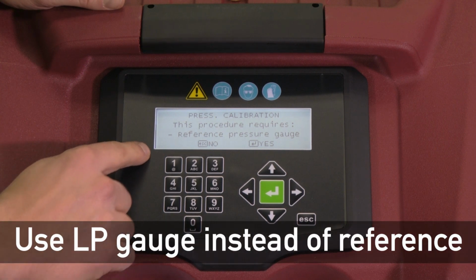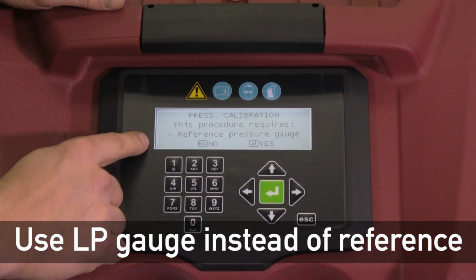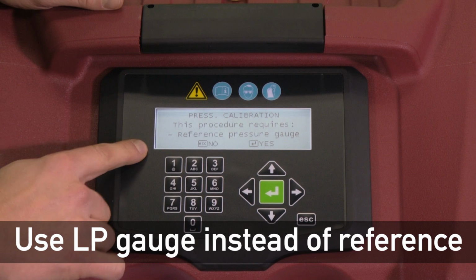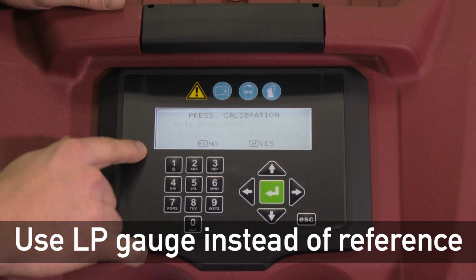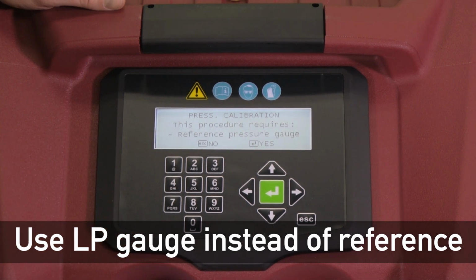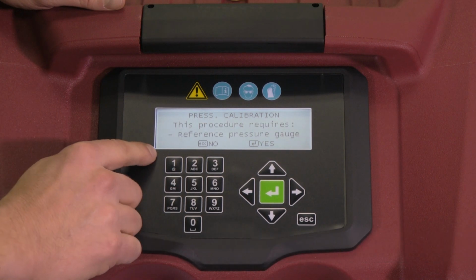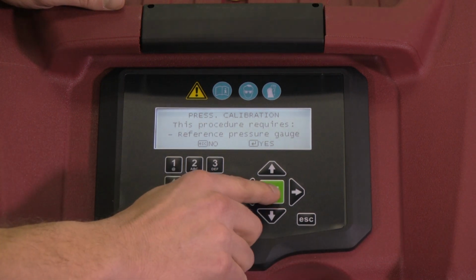It's going to say the procedure requires a reference pressure gauge, but this is possible to do in the field without a pressure reference gauge, just by using the LP gauge. So that's what we'll end up using instead of a pressure reference gauge. So we're going to say yes to this.